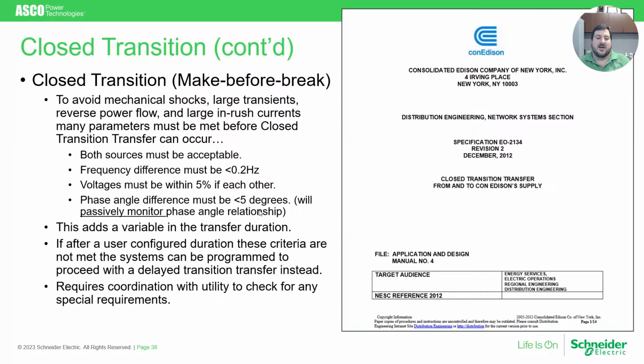So that's how the concept of the passive synchronization that happens with closed transition happens, allowing for a safe parallel operation. Additionally, there's all sorts of protection and time delays that ensure that if the parallel operation lasts for an extended period of time, longer than is safe, it will trip outputs on the transfer switch that are meant to be connected to circuit breakers elsewhere in the system to end the parallel operation.